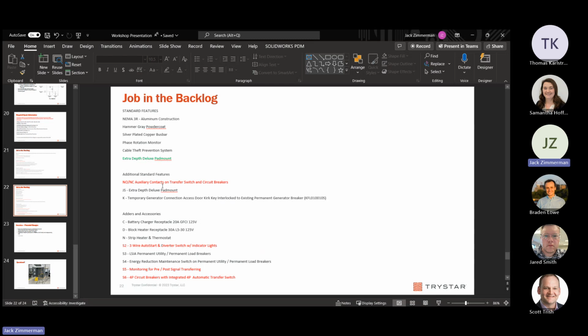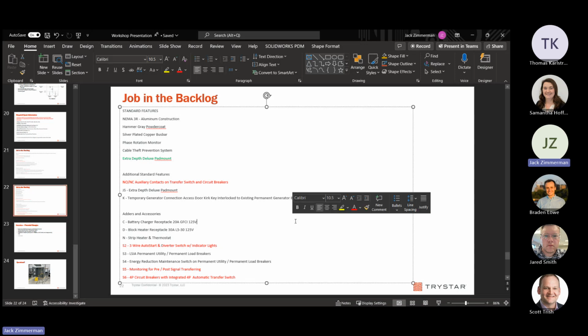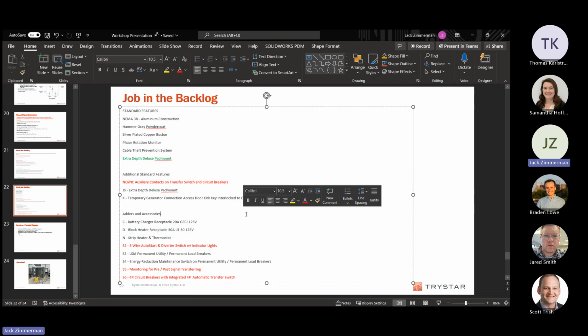Did you just say that if it were 3,000 amps or higher and 4-pole, it would not fit? I think it's 3,200 frame size. Frame size 3, 4-pole won't fit in the deluxe pad mount. How are we specifying that to say no, because that means we're going to have to redesign the enclosure?